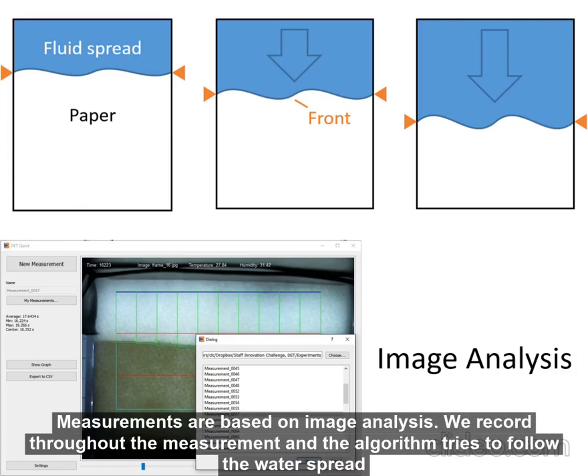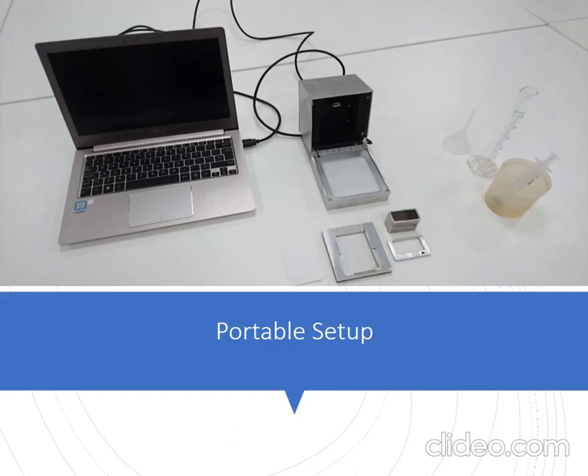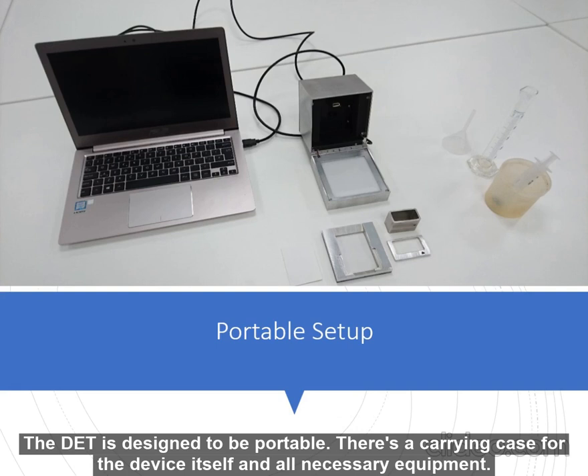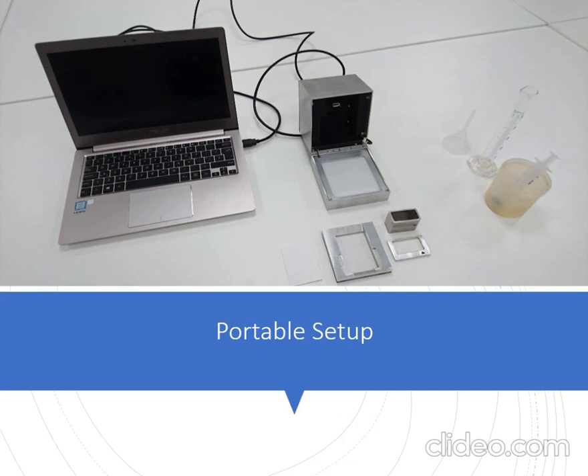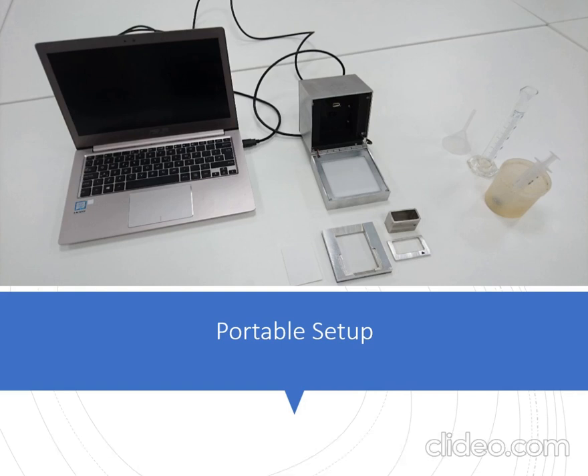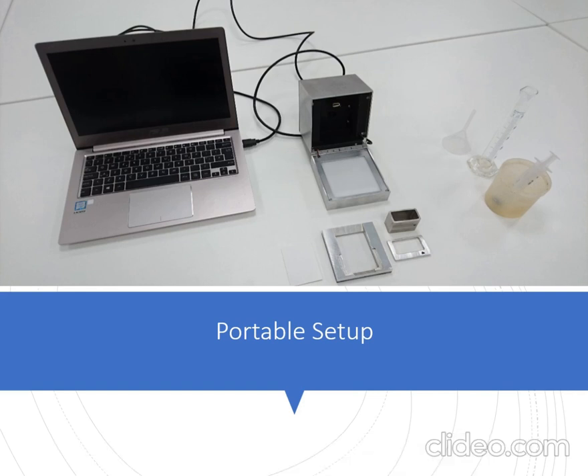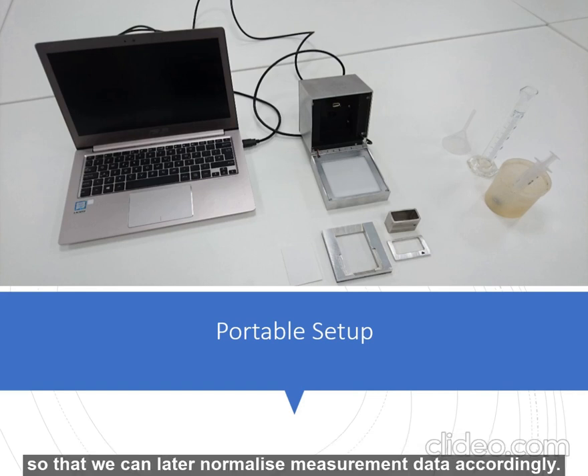Measurements are based on image analysis. We record throughout the measurement, and the algorithm tries to follow the water spread in the filter paper and generate data points with time and position. The software is developed in-house in Salford. The DET is designed to be portable — there is a carrying case for the device and all necessary equipment. Any standard Windows laptop will power the device via USB and run the software. Because measurements are impacted by outside temperature, a temperature sensor was added to normalize the measurement data accordingly.